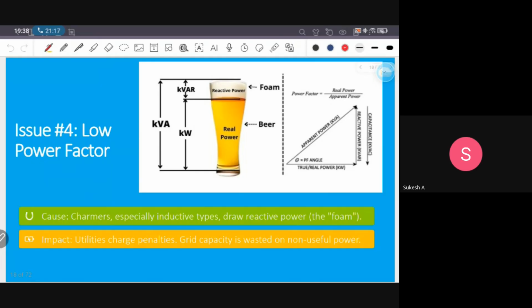And another issue is low power factor. We have already seen this beer analogy. So power factor plays another role: keeping the true or real power constant, let's say K, when the reactive power increases, the apparent power also increases, and the power transferred through our distribution lines will increase, and the heating loss and energy loss through the transmission lines and transformers will increase. So this is also another issue, and especially when using inductive loads, the reactive power is the problem.